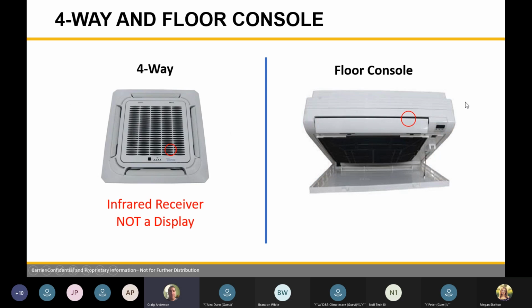So 4-way ceiling cassettes, floor consoles, they do not give error codes. The infrared things that are on there are just the infrared signal for the remote controls. So they will not give you an error code. Your error codes will be on your remote control or your outdoor unit. So if you're trying to figure out it's not giving you an error code, it's not going to. You have to go to your remote or your outdoor unit.